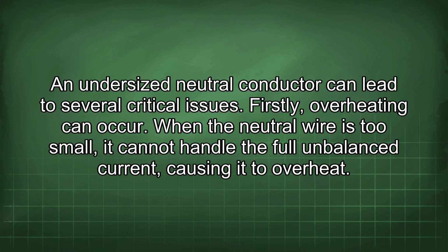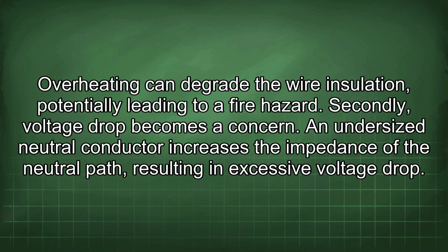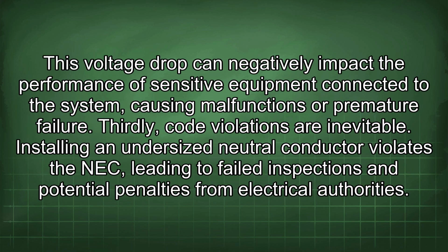Firstly, overheating can occur. When the neutral wire is too small, it cannot handle the full unbalanced current, causing it to overheat. Overheating can degrade the wire insulation, potentially leading to a fire hazard. Secondly, voltage drop becomes a concern. An undersized neutral conductor increases the impedance of the neutral path, resulting in excessive voltage drop. This voltage drop can negatively impact the performance of sensitive equipment connected to the system, causing malfunctions or premature failure.